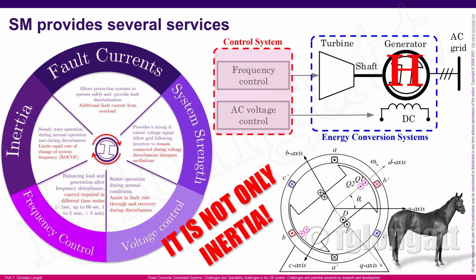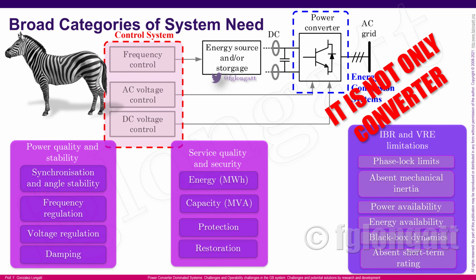But now with the power converter, the history starts to change. Power converters are extremely different. They don't have any kind of mechanism in order to store energy. They require a primary energy resource. They require so many controllers, including very fast controllers related to the currents and to commutation, but also slower controllers like frequency control, AC voltage control, and DC voltage control.